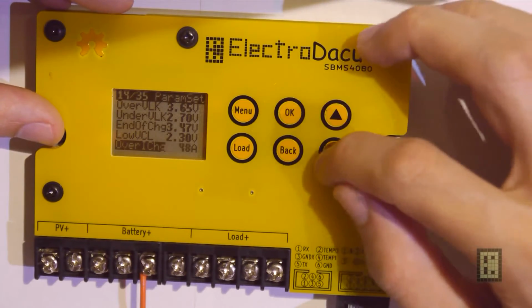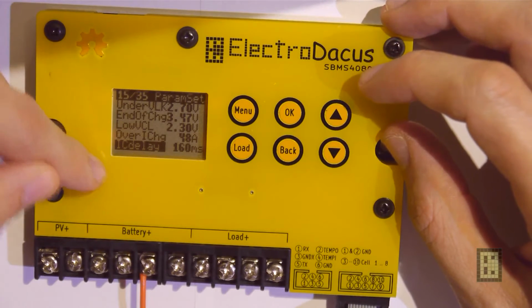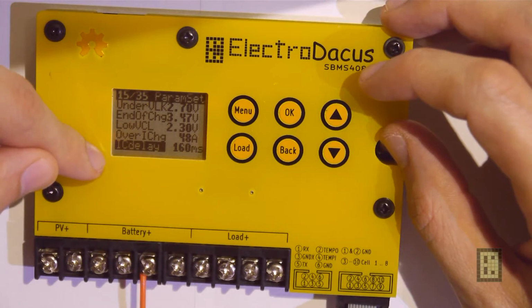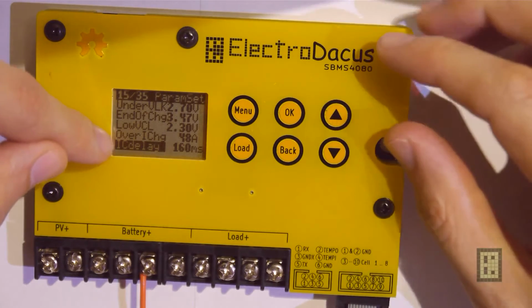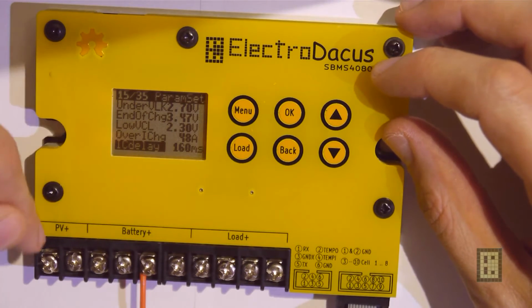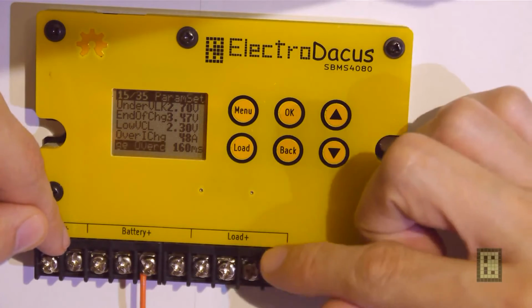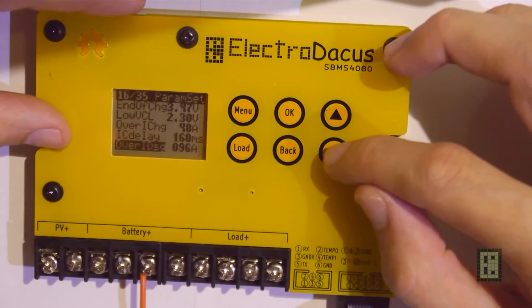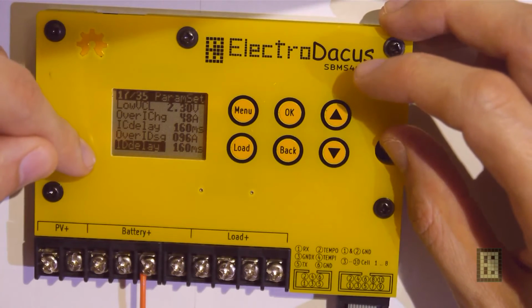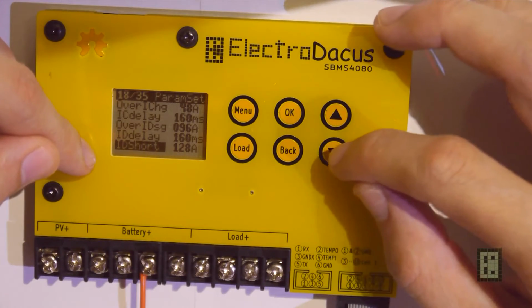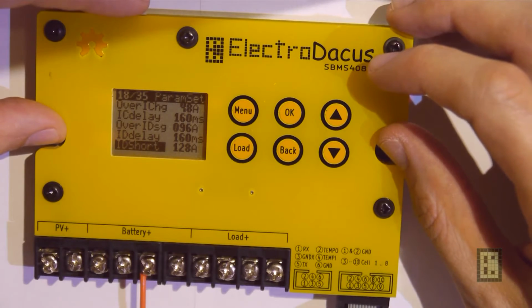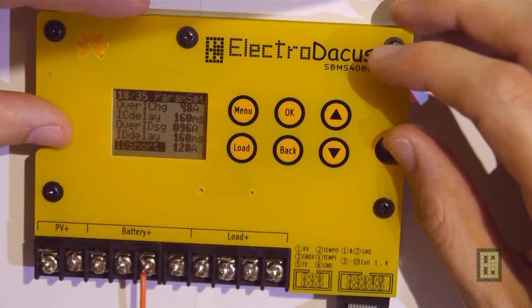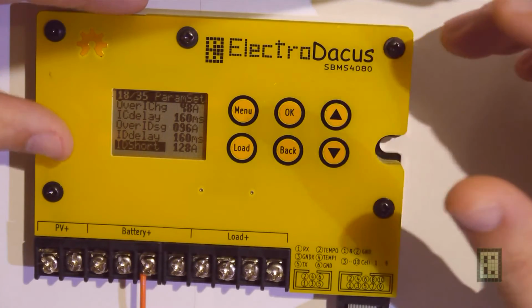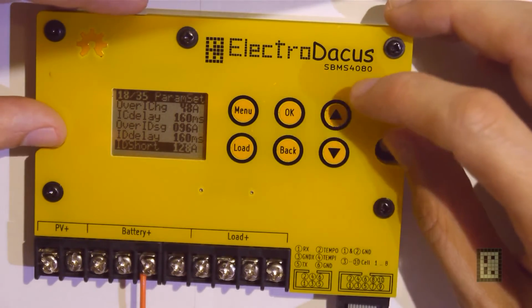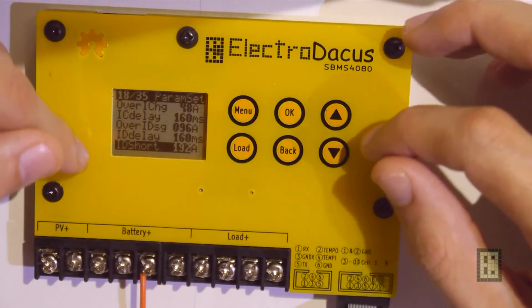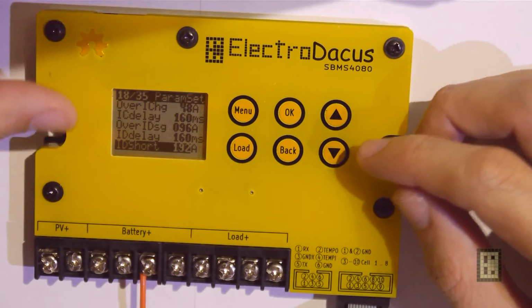Anyway, again, this delay is in milliseconds. It's the time it will wait after this threshold is exceeded before switching off or cutting off the charging or discharging MOSFET. And the same is valid here. And there is a short circuit current also for discharging, of course. And this one is set by default at 128, but you can set it higher, to 192, if you have any problems.